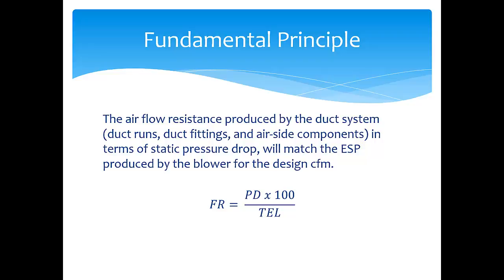This all comes down to the fundamental driver for duct sizing: the pressure drop causing resistance to airflow must match the external static pressure produced by the blower for the design CFM. This airflow resistance causing pressure drop comes from the duct runs, the fittings, and any air-side components. This is captured in what's called the friction rate equation, so let's look at this in more detail.